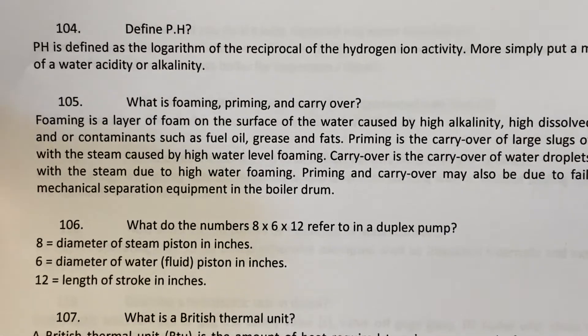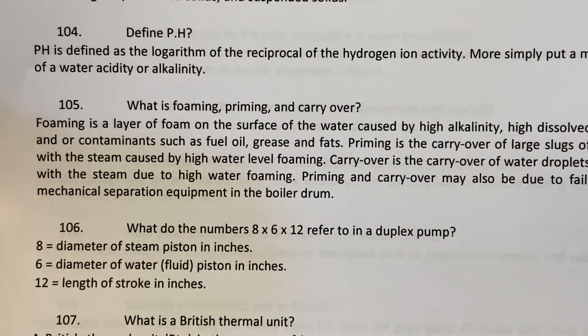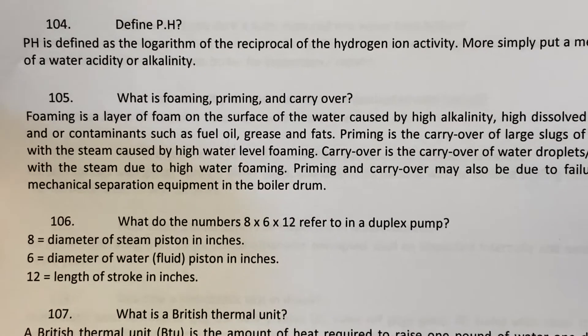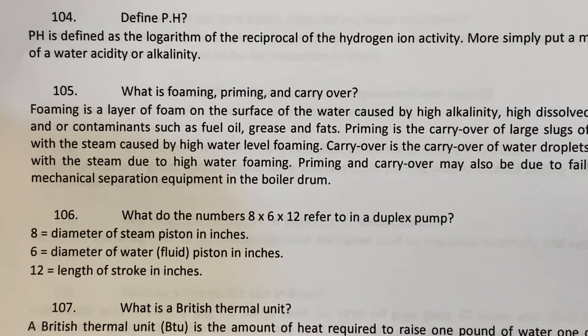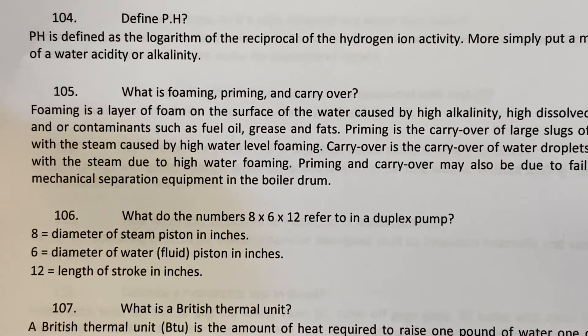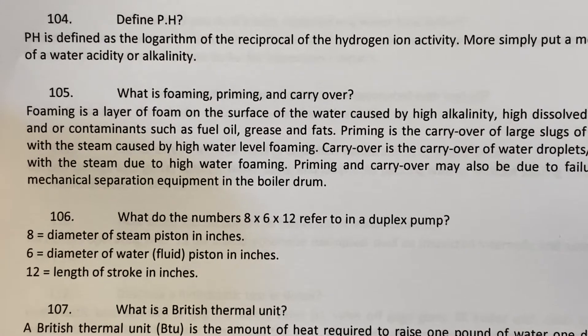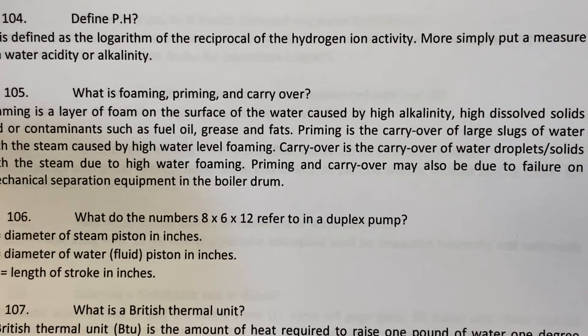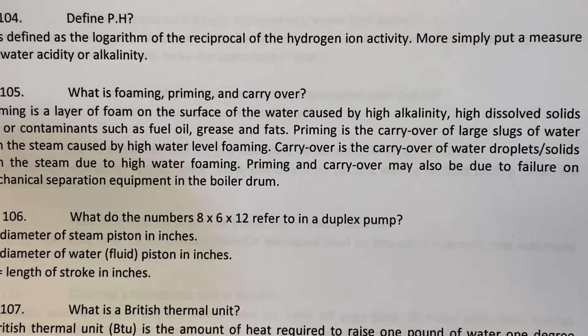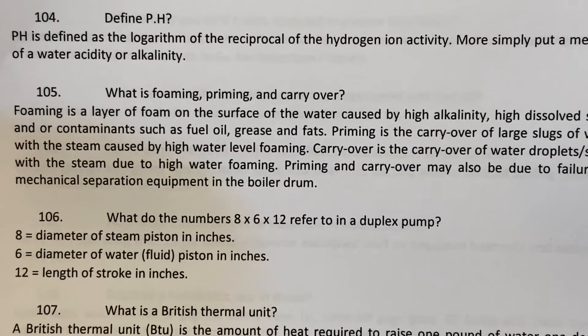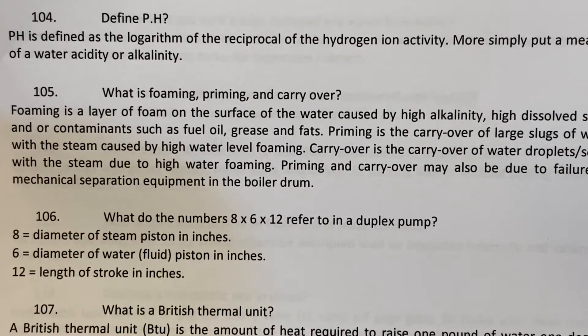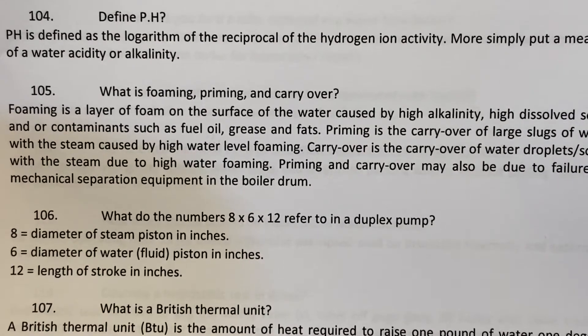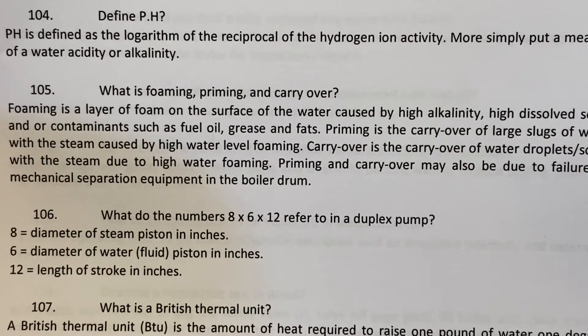What is foaming? Foaming is a layer of foam on the surface of the water caused by high alkalinity, high dissolved solids, and/or contaminants such as fuel oil, grease, or fats.